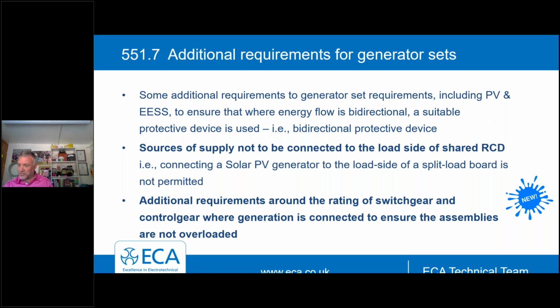We talk about the source of supply should not be connected to the load side of any RCD providing additional protection that is shared with other circuits. So, for example, where an RCCB on the load side is in a split load board, and you might have, for example, solar PV generator on that load side and also other circuit breakers. So is that the end of the split load board? Be interested to know your thoughts.